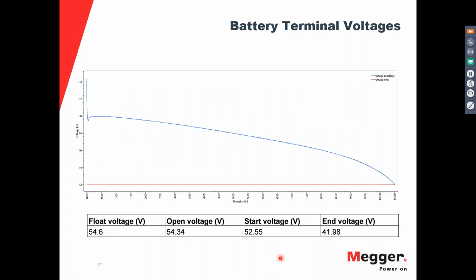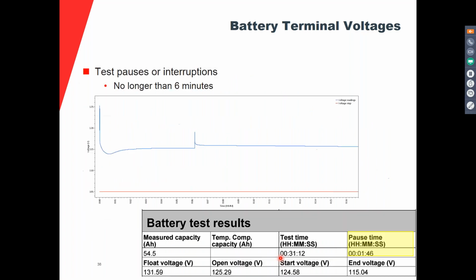So here we see a typical result again, the discharge curve and the voltages at different stages. Here is another example, and this includes a pause. So the standard allows for a pause in the test, especially to bypass a cell, to remove a cell from the string, because this cell might be failing.